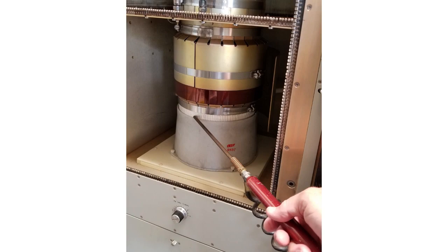When you shut that transmitter down, you want to make absolutely certain that there's no voltage remaining or you're going to really hurt somebody or better yet kill them. So that's why most all of these big broadcast transmitters that were tube-type came with one of these shorting sticks with it. This one's attached right on the front of the transmitter. And no resistance, it's just straight to ground.